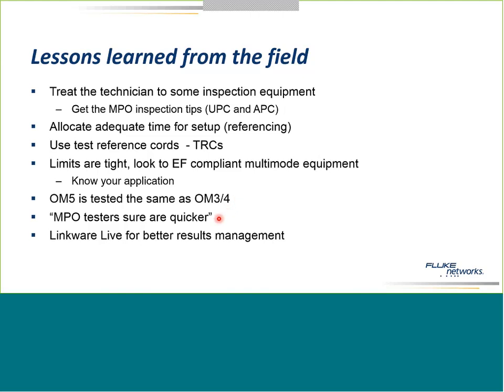If you have a lot of MPO trunk cables to test, boy, a dedicated MPO port on your tester sure is going to be faster. Again, you have a container load of MPO trunk cables to test before you put them in the data center. A multi-fiber is just going to be worth your time to be running those tests faster. You have 1, you have 2 MPO trunk cables to test. Sure, use your OLTS. The cost difference may not justify that.